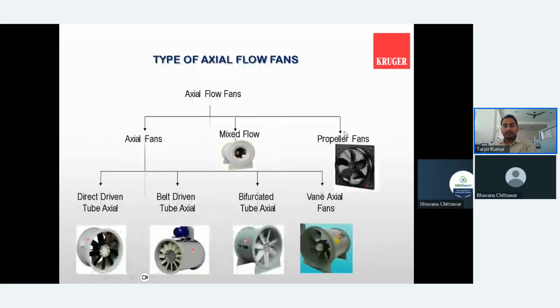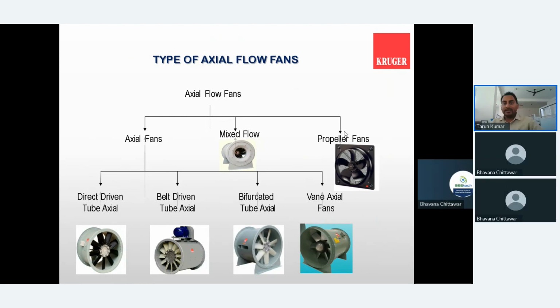Further to that, there is the axial fan, and in axial fan also there are multiple kinds of blade configuration and construction. There is the direct driven tube axial fan, then belt driven tube axial fan, then bifurcated tube axial fan, and vane axial fan. We have also upgraded one more model, the mixed flow fan, which is the combination of the axial as well as the centrifugal, and that too has a certain purpose and application. In axial fan there is also one more segment, the propeller fan. So mainly there are two segments: one is the centrifugal fan and the second one is the axial fan.